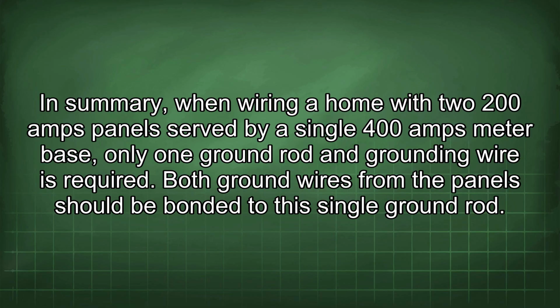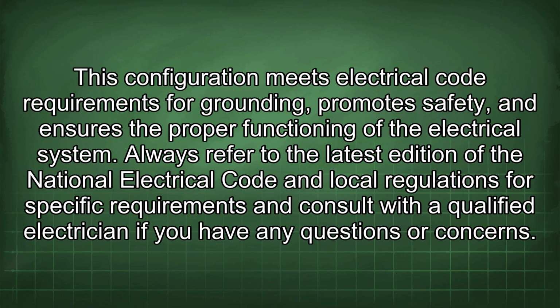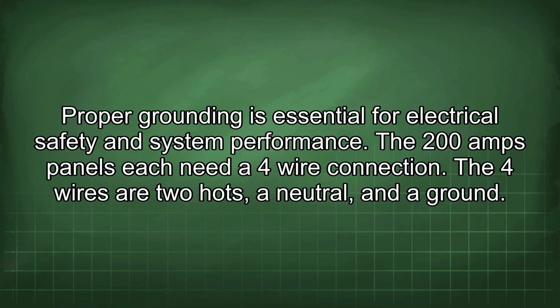In summary, when wiring a home with two 200 amp panels served by a single 400 amp meter base, only one ground rod and grounding wire is required. Both ground wires from the panels should be bonded to the single ground rod. This configuration meets electrical code requirements for grounding, promotes safety, and ensures the proper functioning of the electrical system. Always refer to the latest edition of the National Electrical Code and local regulations for specific requirements, and consult with a qualified electrician if you have any questions or concerns. Proper grounding is essential for electrical safety and system performance.